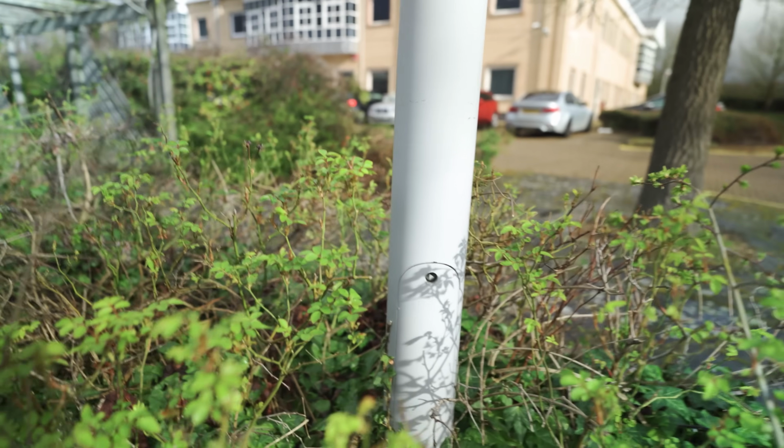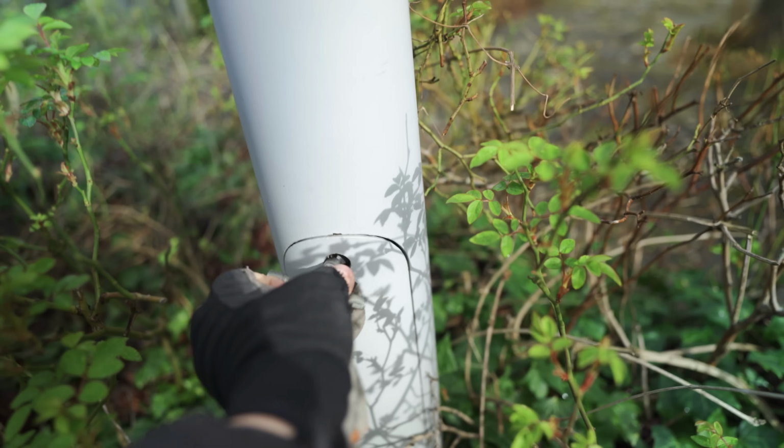It may also just clear completely when I pull all the loads. It might clear, and then that might mean that it's an issue high level on one of the lampposts. I mean, some of them are full of water and stuff like that. We'll get some covers off and we'll see how we go. What's the chances that this is going to fit? And it does. It does.